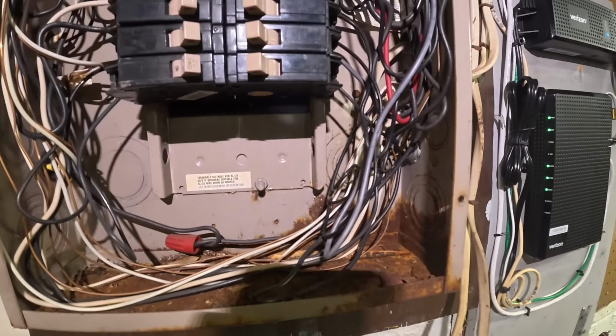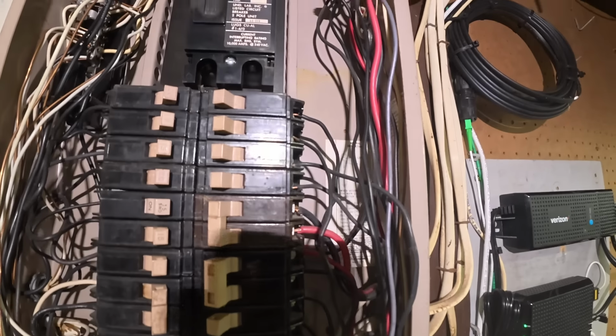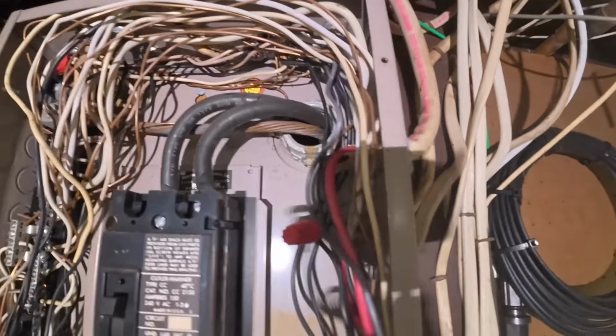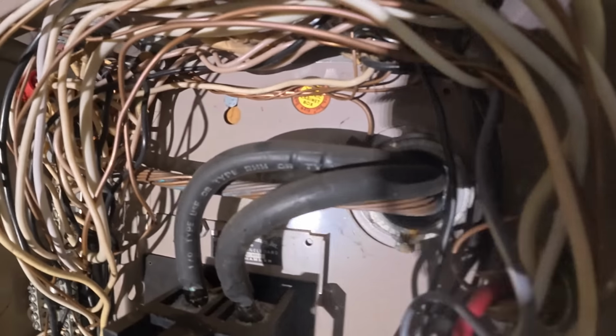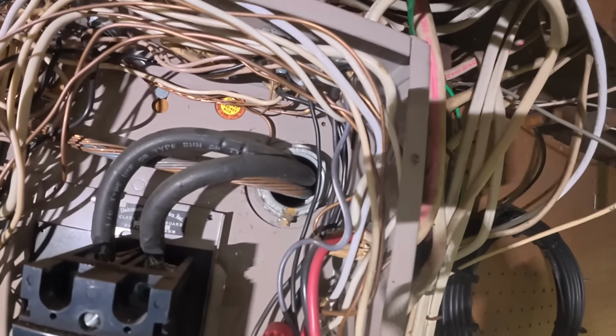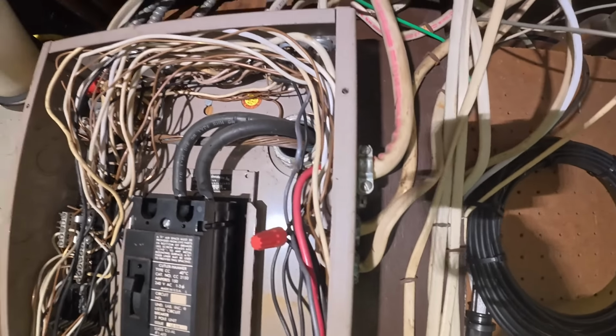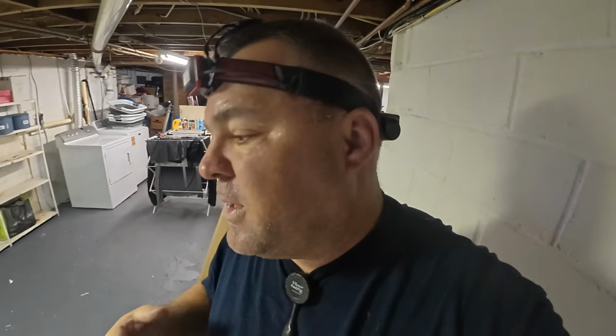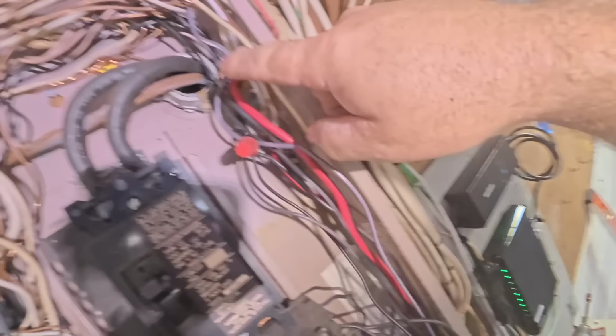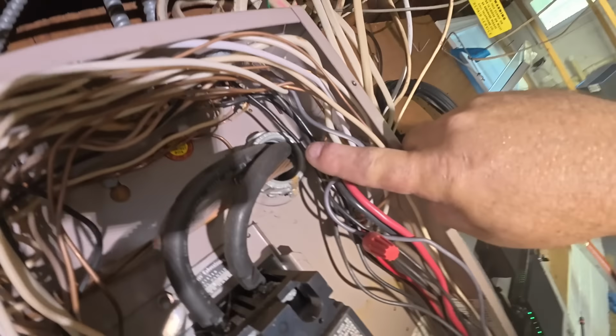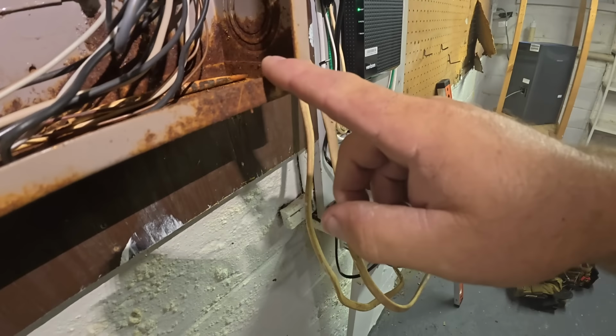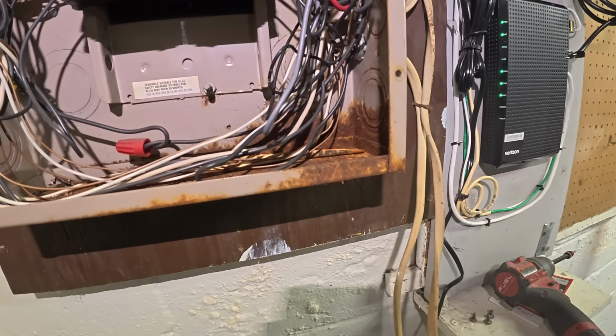If you look right up above from where the service entrance conductors enter this enclosure, it's right here. You can see, well, hopefully maybe you can't see, but I could tell that there's no sealant in that entrance. So when the warm air in the wintertime reaches the cold air outside, in the outside portion of the service, condensation forms. And when the condensation forms, it's going to drip down from this nipple where it enters, where the condensation is happening, straight down into this puddle down at the bottom here, and then you see this rust.